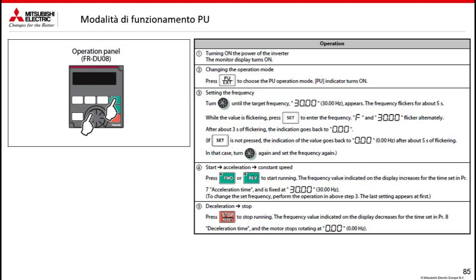Let's look at an example of piloting modes, so how to control the inverter. First of all, the PU mode. To go there, you turn on the inverter, you will read EXT, you press PU/EXT, and it will go to PU. You can pilot the inverter 100% in PU mode. So you set the rotation of the motor directly from the panel unit.